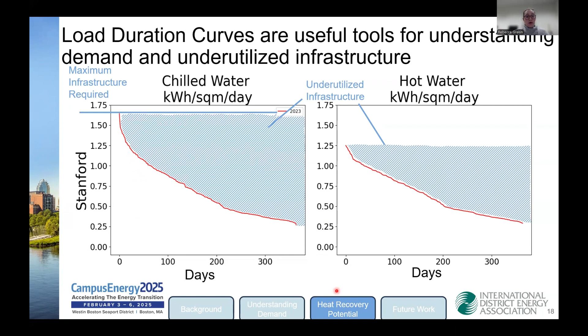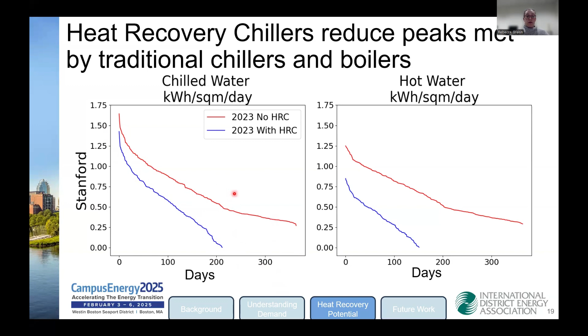What happens to this load duration curve when you implement a heat recovery chiller? Here you can see again for Stanford, the red line is with no heat recovery chiller, and the blue line is with the heat recovery chiller. You can see that there are peak power savings, so the amount of demand that must be met with traditional chillers and boilers reduces on any given day. And the actual number of days that your traditional chillers and boilers are running has been reduced quite a bit. With the heat recovery chiller, you have the heat recovery chiller running most of the year, and the traditional boilers are only needed about 200 days out of the year instead of 360. And for any given day, if the boilers or the chillers are running, they are producing less than they were without the heat recovery chiller.